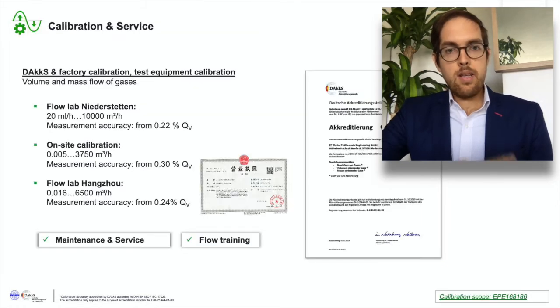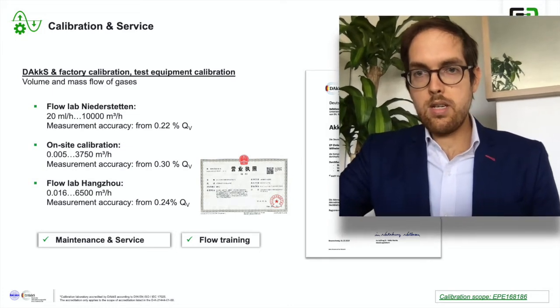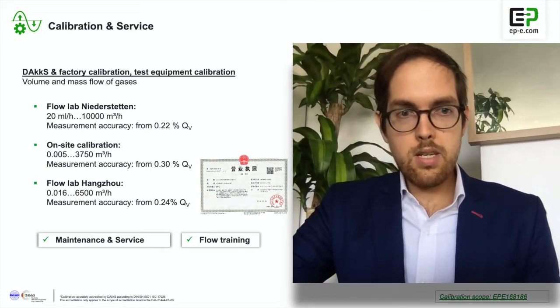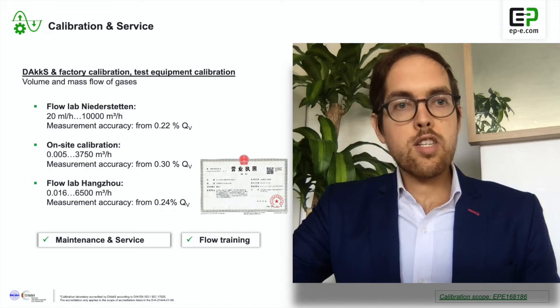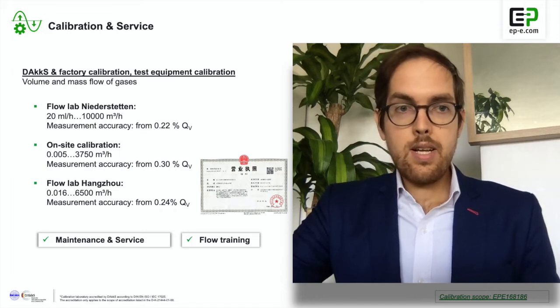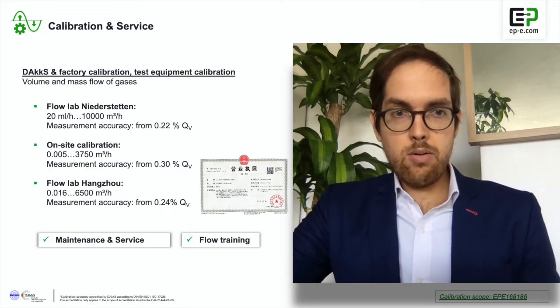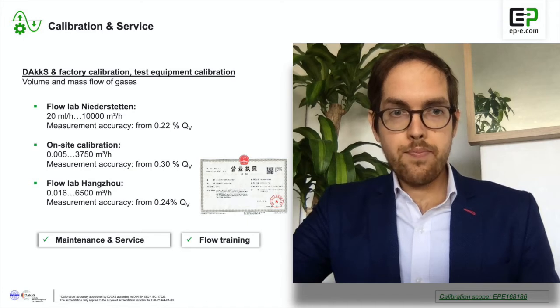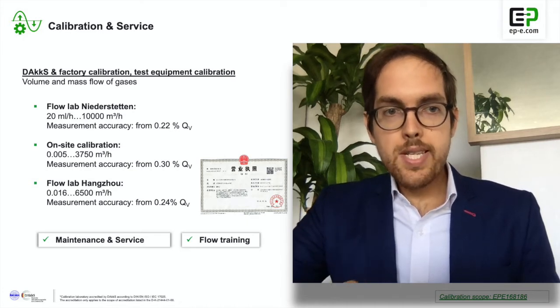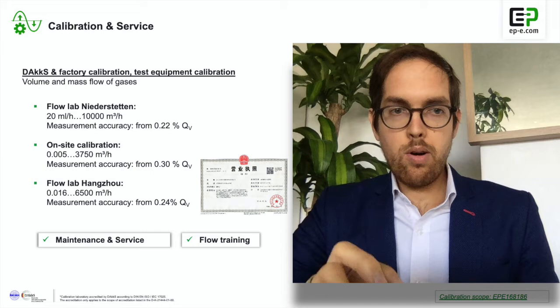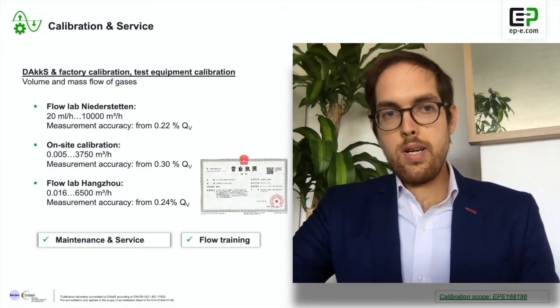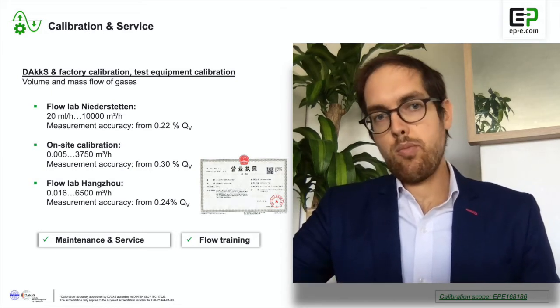Here we see our certification and our flow range, which we can calibrate in Niederstetten. This is 20 milliliters per hour to 10,000 cubic meters per hour. On site, it is 0.005 cubic meters per hour to 3,750 cubic meters per hour.